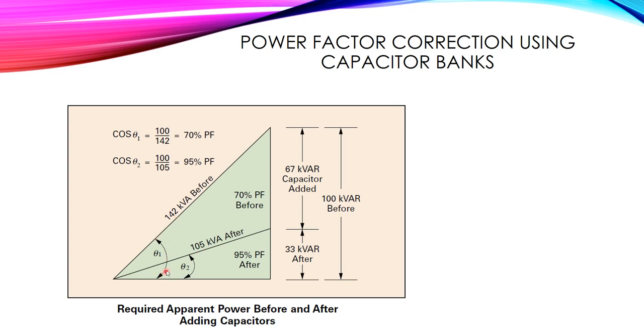The angle theta, whose cosine represents the power factor, was large before correction. After power factor correction, theta 2 is smaller, so cosine theta 2 is higher than cosine theta 1. Previously, 100 kilowatts divided by 142 kilovolt-amperes gave a 70 percent power factor. After adding the 67 kilovar capacitor bank, the apparent power from the grid is now 105, so the power factor improves to 95 percent.